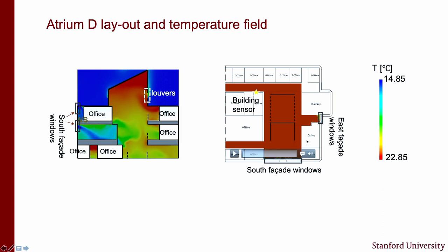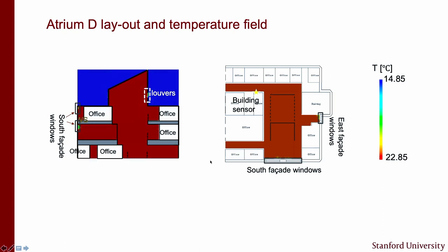Now, if you look at the floor plan, this is on floor 2, and I'll play this video as well. This is where our building sensor is that we were going to use for validation of our models. When you play this, you see these two jets of air coming in. They drop down, so you don't see them in this plane, but then you see how they start to fill the space with cold air. Clearly, on average, this space is cooling much faster than our building sensor.